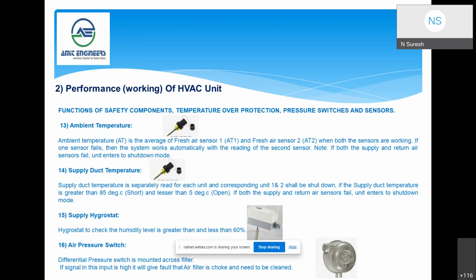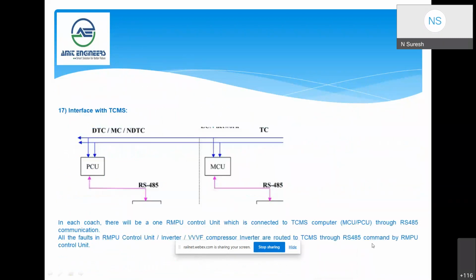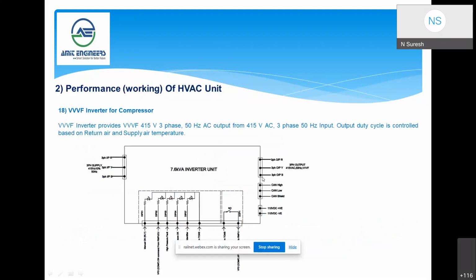As I briefed you, a differential pressure switch is mounted across the filter. If the signal in this input is high, it will give a fault: the air filter is choked and needs to be cleaned. This is a brief schematic of how the controllers are connected to the TCMS. This is a brief inverter schematic.